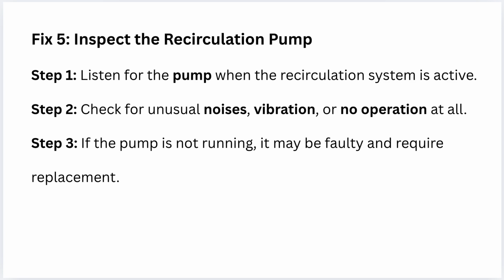Fifth one is inspect the recirculation pump. Listen for the pump when the recirculation system is active. Check for unusual noises, vibration or no operation at all. If the pump is not running, it may be faulty and require replacement.